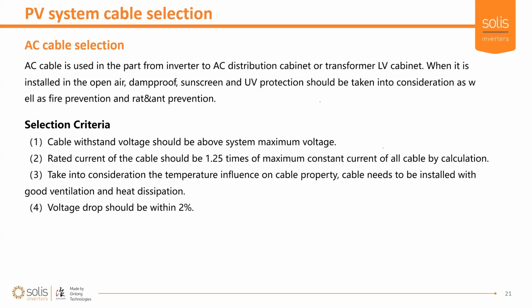The cables need to be able to handle the currents. That's an obvious one. On the next slide, I'll go through some quick calculations on how to calculate this. Temperature of the cables needs to be considered here, as you often run the cables next to each other or underground or next to something that can dissipate heat, and that will always have an influence on the amount of current that cable can handle. However, your cable manufacturer usually gives you good data on how to work this. They give you a table and they tell you how many cores you're running per conduit, etc., and it's usually quite easy.